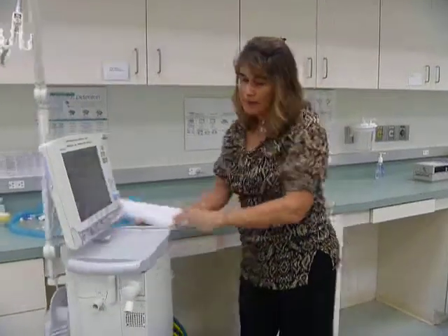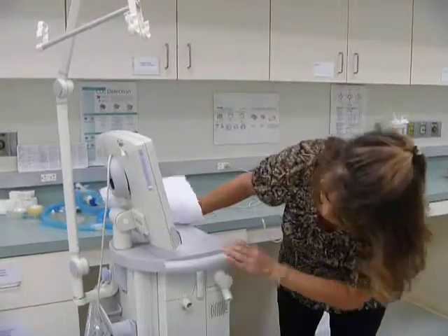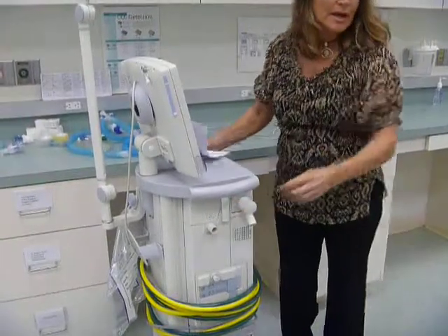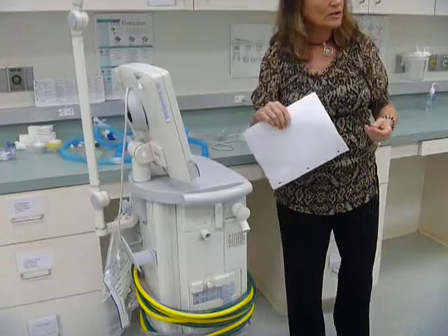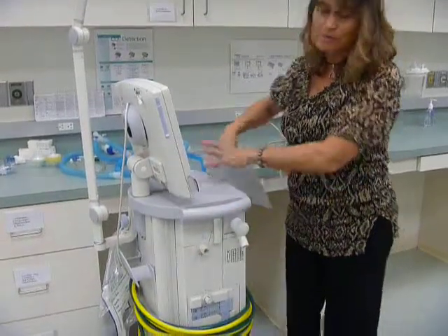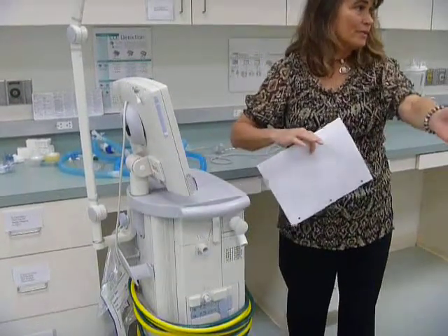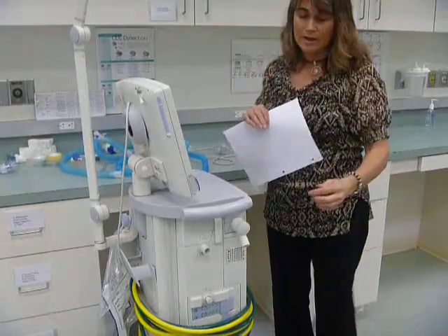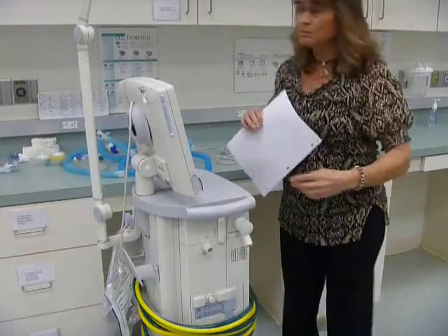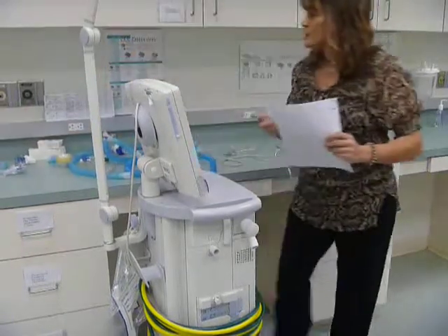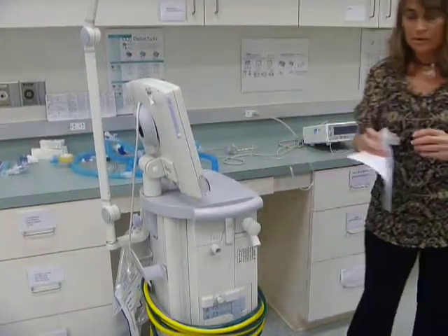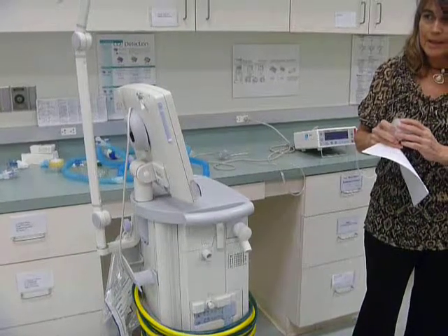On the Servo i, it says inspiration, and it has an arrow pointing to the patient to show that the arrow is going into the patient. So that's where the fresh supply of air comes out of the ventilator to go to the patient. So that's the inspiratory port. And there's going to be a filter placed on it.